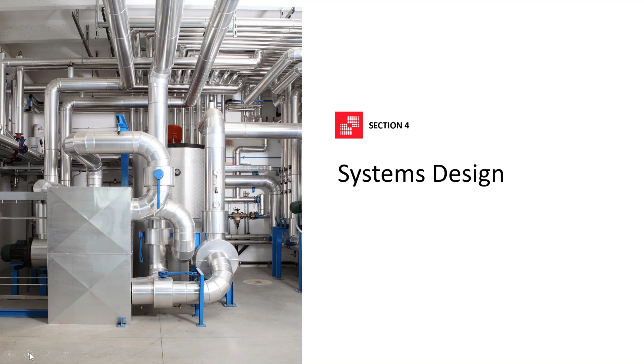Okay, moving on to some of the system designs. This is a schematic of the basic mechanical system, and the approach is to separate ventilation from heating and cooling. We have centralized energy recovery ventilators that provide fresh filtered air to each apartment continuously. The exhaust routes back to those ventilators, and heat is recovered when needed.